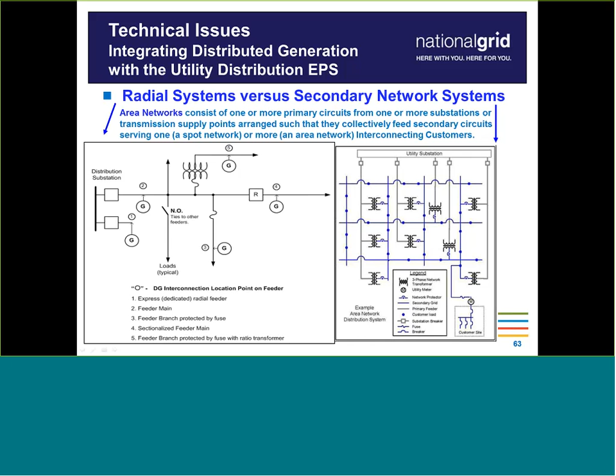So here you got a radial feeder. This is your station breaker. You got some taps here, ties to other feeders. You got a fuse tap, another sectionalized line. That's fine. That's simple enough to deal with. It generally has a good amount of load on it. Everything's great. Then you get to a secondary network system like this, and you've got network protectors that are coordinating with each other. You've got all these transformers here, and you've got this sort of tie into the substation through a bunch of other feeders. So if you have those, they're way more complicated than this radial feeder situation here. So we will do a study for it. I can tell you though, it's going to be a lot more complicated than a radial system interconnection.